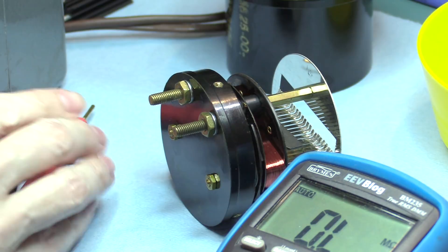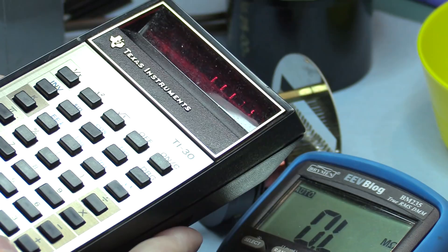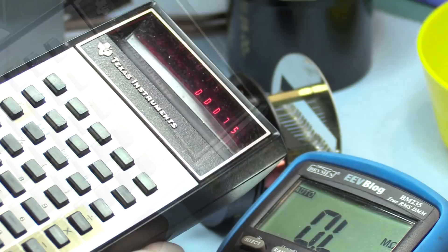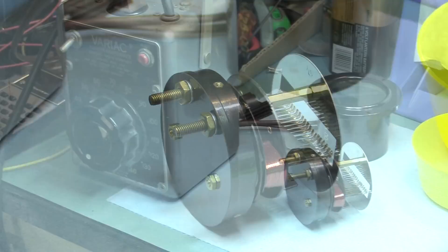Let's power this up and see how it works in real life. The first thing I do is get the static resistance of the coil: 16 kOhm. So it's designed to pull very little current, so at 120 volts it's going to be 7.5 milliamps. Hardly anything at all, which you'd expect for something that would be designed to be on all the time, probably in circuit.